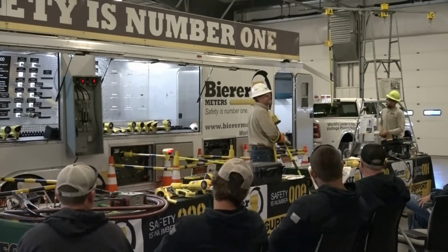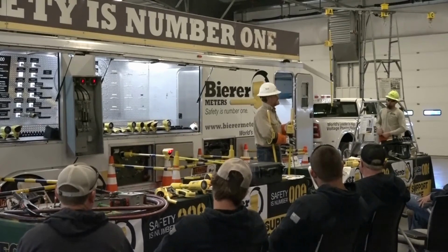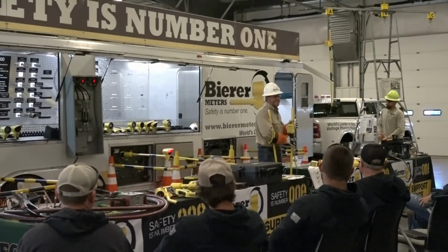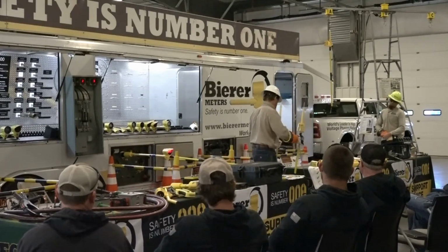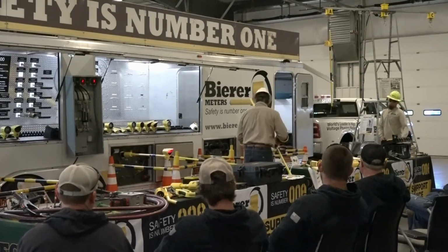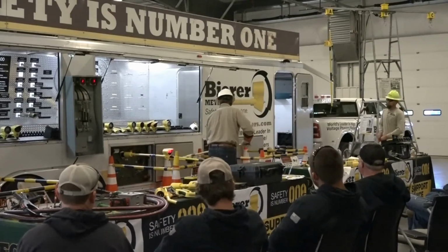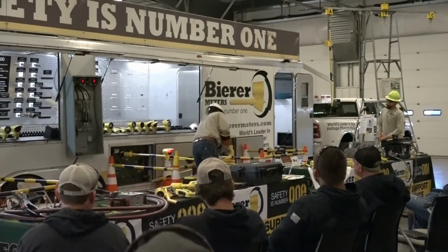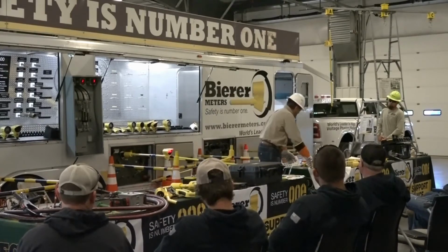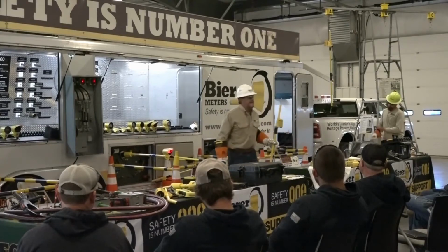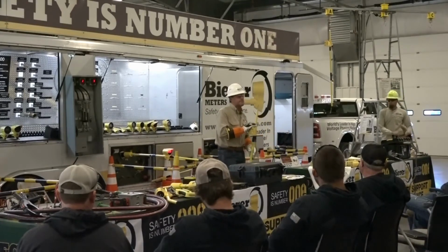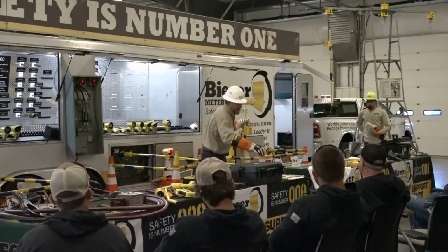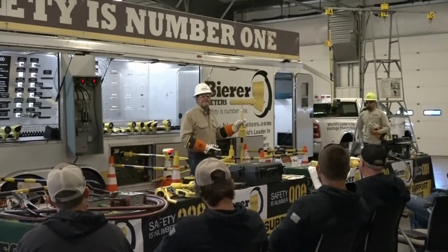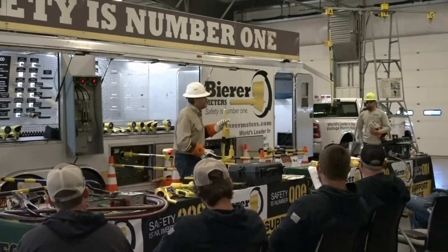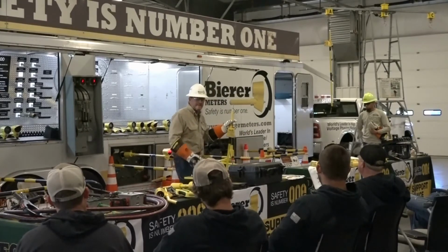Dylan's going to use a PD25. This is the most accurate voltage indicator on the market, one of Walter's 17 patents. It's corded, so we're going to go phase to ground. The secondary probe will go to the ground, which we're calling the trailer. You can use this device for testing lightning arresters, to verify your regulator neutrals in the neutral position or not. You can high pot with it. You can find your leading phase out in the field with it. You can de-energize conductors with it, capacitors.